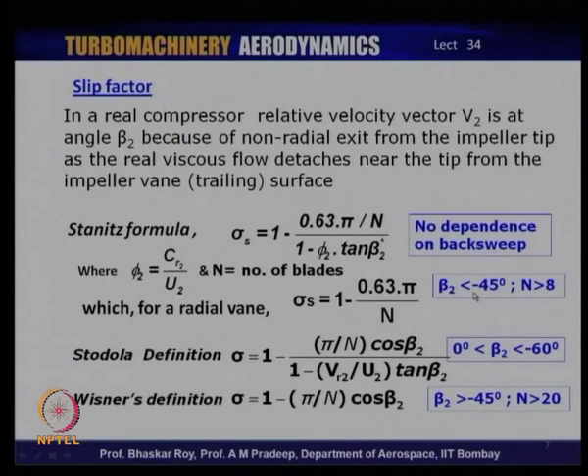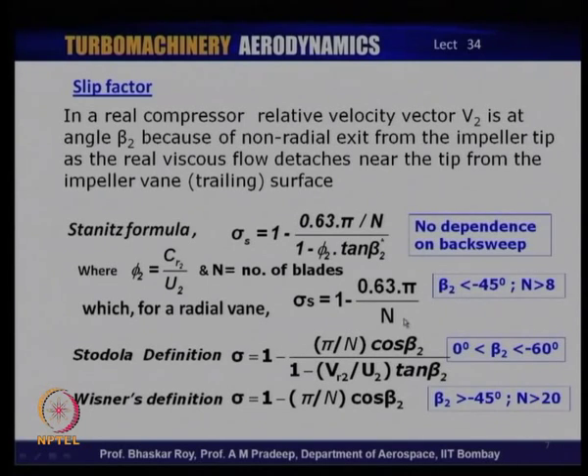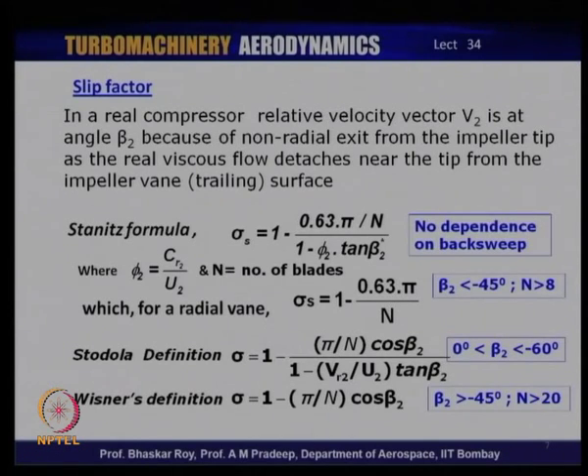In that kind of situation — backward sweep less than −45° and more than 8 blades — the simple formula is found to be quite valid. However, if the backward sweep is more than 45° or the number of blades is less than 8, this formula may not be a very useful indication of the slip factor. It is generally found that the slip factor does vary a little with the value of β₂, especially since modern compressors are going for backward-swept blades rather than radial-vane machines. As a result, the utility of earlier simple slip-factor formulas needs to be re-evaluated for modern designs.